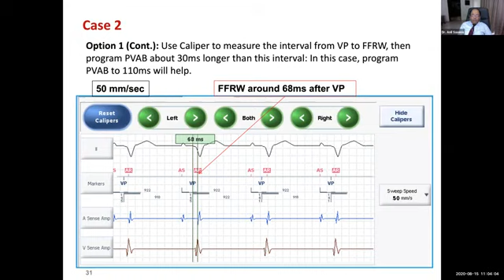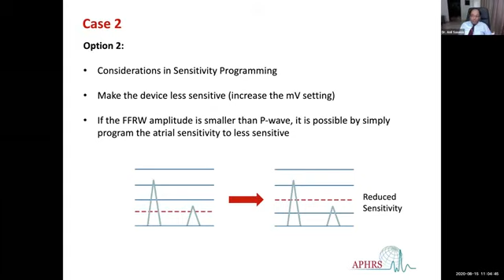The second way to solve this problem is if we have the atrial signal taller than the ventricular signal, and the sensitivity setting is quite high so that both are being sensed. We can reduce the sensitivity by programming a higher millivolt value, and that will allow us to sense only the atrial signal, and the ventricular signal will not be sensed, so the count will not be doubled. So that can be another way. But sometimes both are of the same amplitude, or even the ventricular signal may be taller, then this will not work. So in a rare situation, we may even have to replace or reposition the lead.